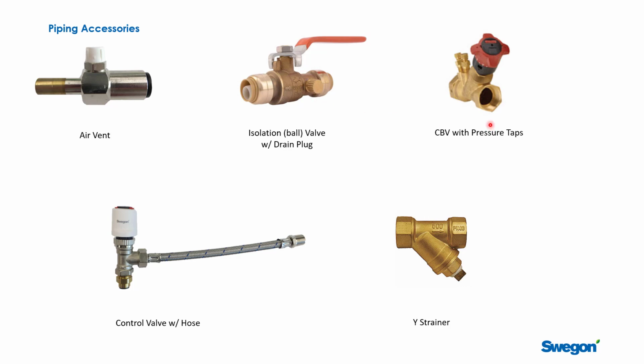You will on occasion see circuit setter balancing valves being used. It's nice to have the taps, but remember these flow rates are down around 1 GPM. This is a fairly expensive device. It's a really nice thing to have, but it could run the cost of the project up, and so I wouldn't casually go out and apply them, but certainly wouldn't say it's a bad idea if you're going to do that. Strainers possibly in the systems.